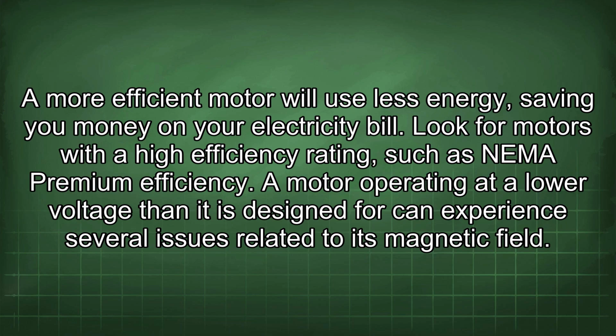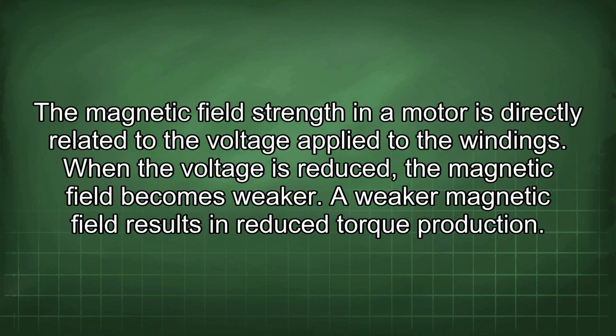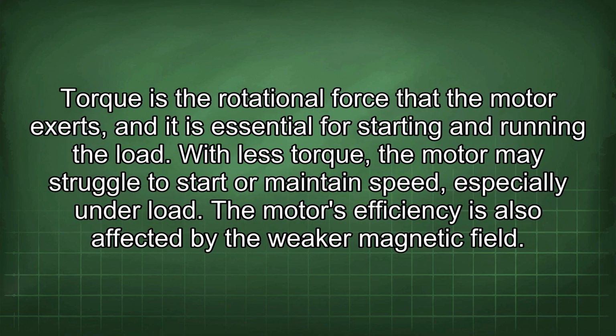A motor operating at a lower voltage than it is designed for can experience several issues related to its magnetic field. The magnetic field strength in a motor is directly related to the voltage applied to the windings. When the voltage is reduced, the magnetic field becomes weaker. A weaker magnetic field results in reduced torque production. Torque is the rotational force that the motor exerts, and it is essential for starting and running the load. With less torque, the motor may struggle to start or maintain speed, especially under load.